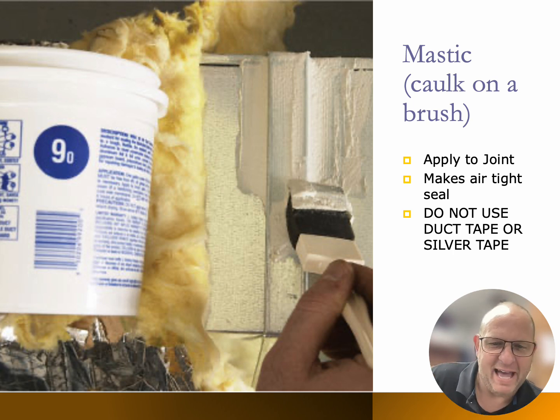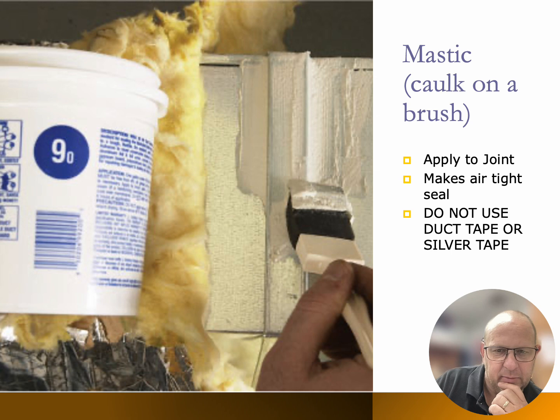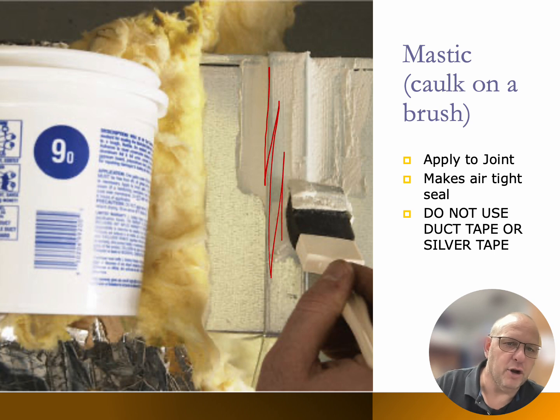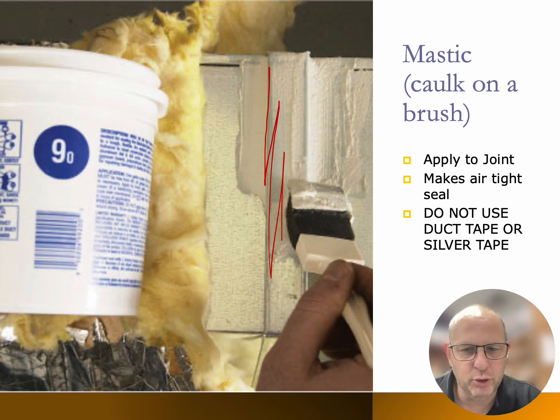So we talked about the mastic that's going to be going on our particular joints for our rectangular duct. Now, right in front of you is a drive cleat. So this right here is a drive cleat. What we're going to do is paint the edges of that drive cleat, and we're going to seal that air inside the ductwork so we don't lose our money that we just put into conditioning that air itself.